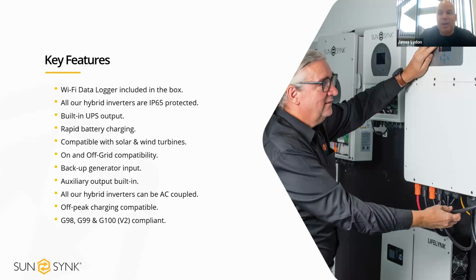Rapid battery charging. The rate at which you can charge the connected batteries with our inverters is always the rated value of the inverter. So if someone's got a 5 kilowatt hybrid inverter and a 5 kilowatt hour battery, you can charge that battery at 5 kilowatt. Whereas, there's some others on the market where if you've got the same setup, you might be restricted to only charge the battery at 3 kilowatt, let's say. Ours will work at 1C and the inverters will always output the rated value of the inverter.